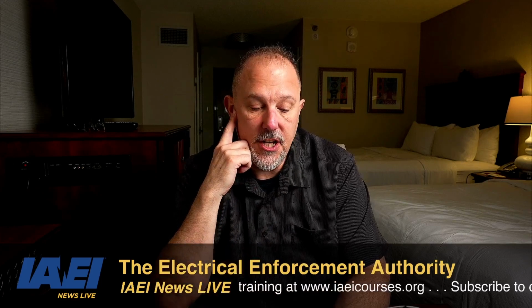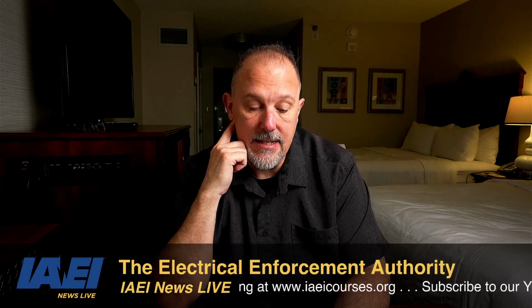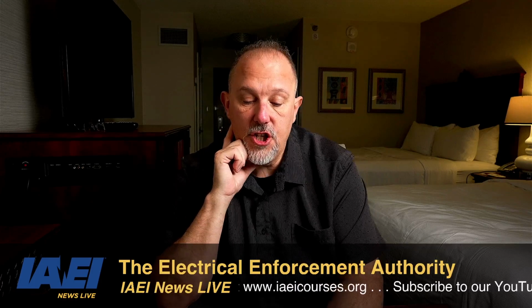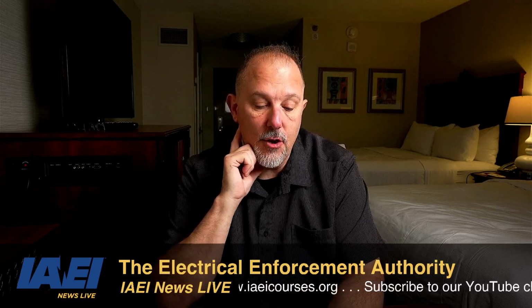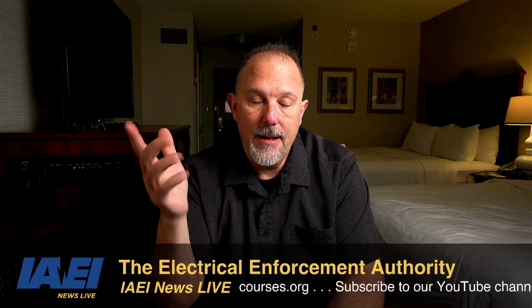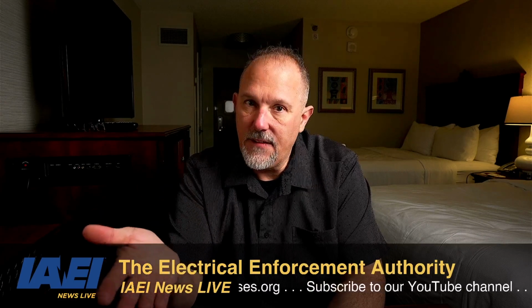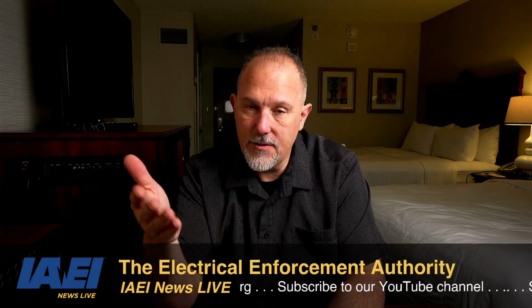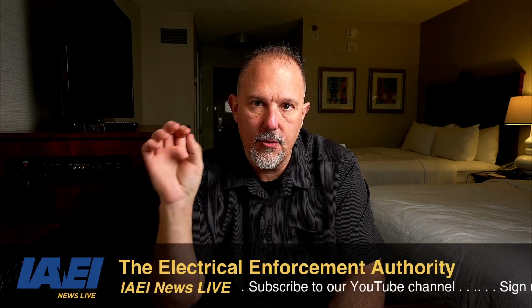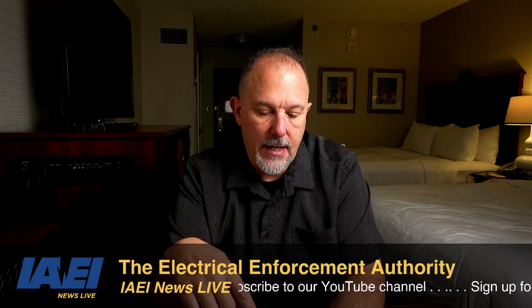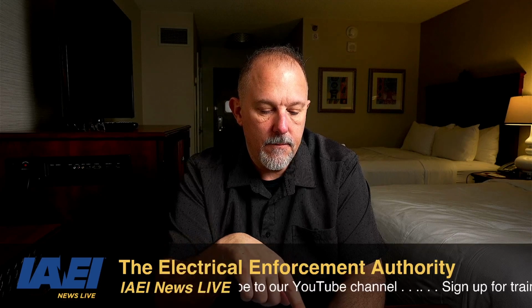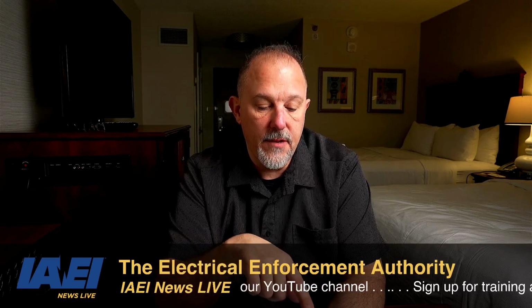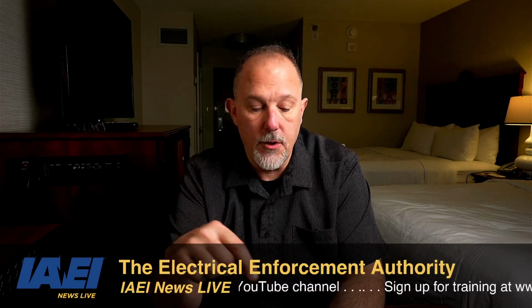65 volts or less: generators operating at 65 volts or less and driven by individual motors shall be considered as protected by the overcurrent device protecting the motor. Again, it's 65 volts. And remember how generators work. So if I shut down that motor, if I protect the motor from overheating, etc., when the generators are delivering not more than 150% of their full load rated current.